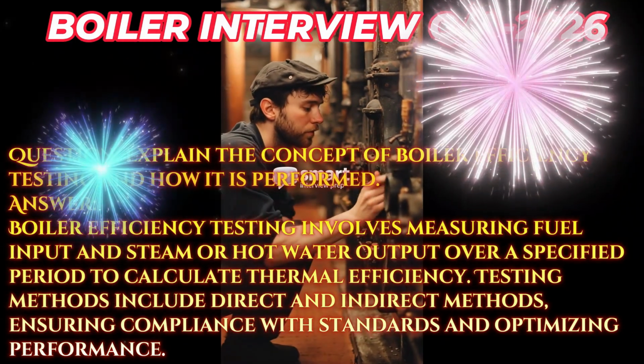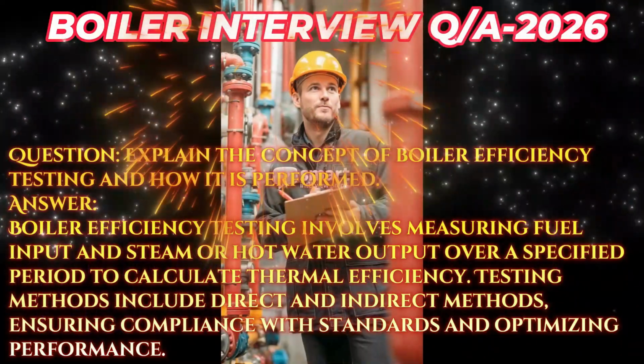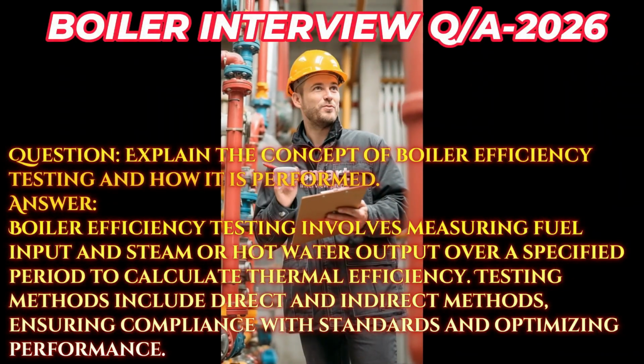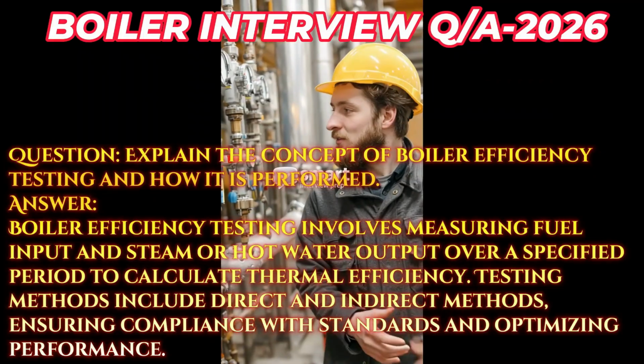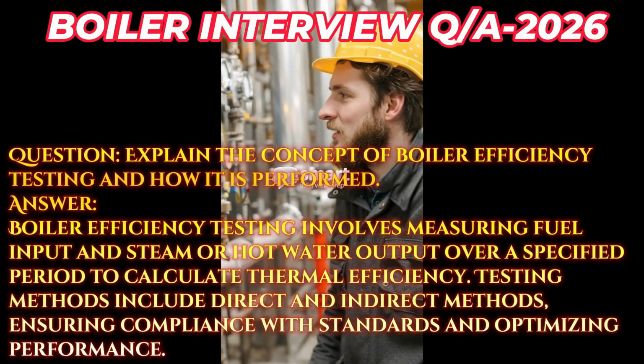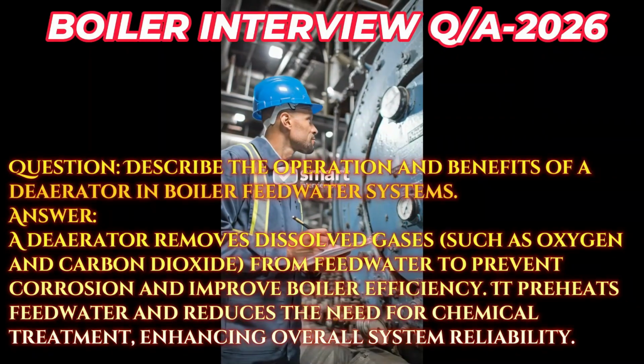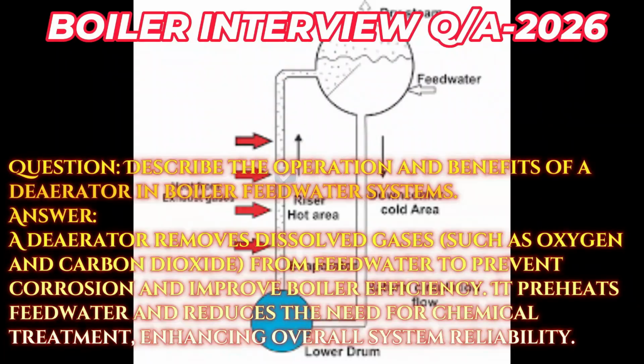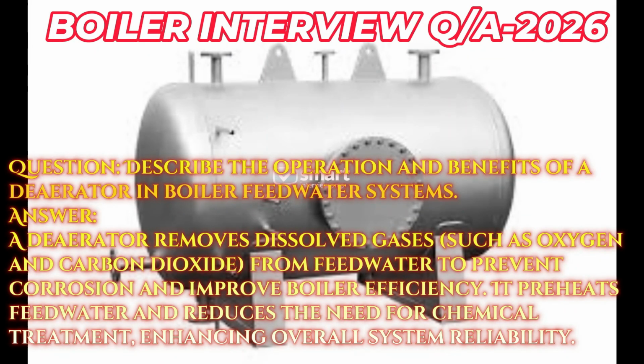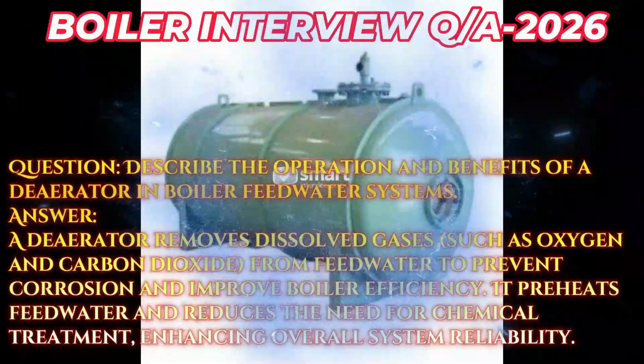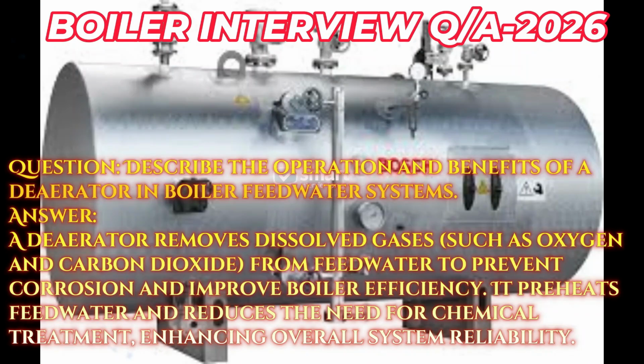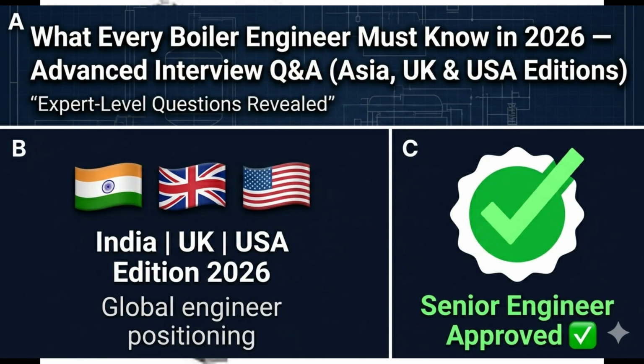Question: explain the concept of boiler efficiency testing and how it is performed. Answer: boiler efficiency testing involves measuring fuel input and steam or hot water output over a specified period to calculate thermal efficiency. Testing methods include direct and indirect methods, ensuring compliance with standards and optimizing performance. Question: describe the operation and benefits of a deaerator in boiler feedwater systems. Answer: a deaerator removes dissolved gases, such as oxygen and carbon dioxide, from feedwater to prevent corrosion and improve boiler efficiency. It preheats feedwater and reduces the need for chemical treatment, enhancing overall system reliability.